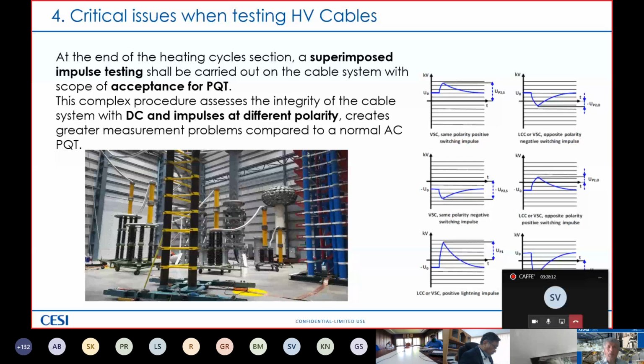Last but not least, to complicate HVDC testing, at the end of the heating cycle section, in case of DC, we have a superimposed impulse test that shall be carried out on the cable system as an acceptance test. This is a complex procedure performed to assess the integrity of the cable system with DC applied, positive and negative, and impulses at different polarities, both positive and negative.